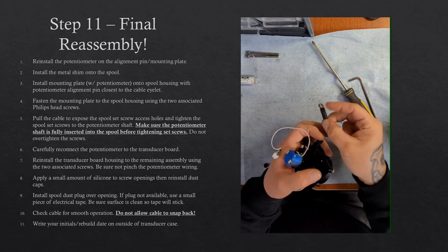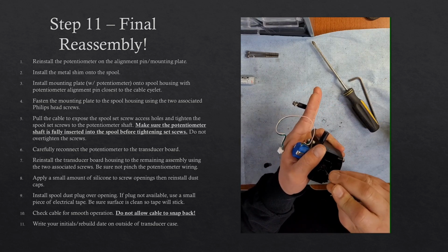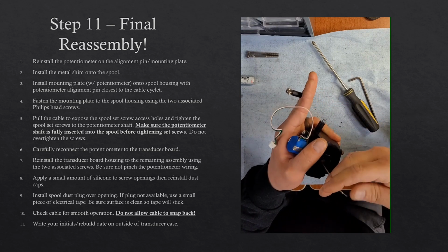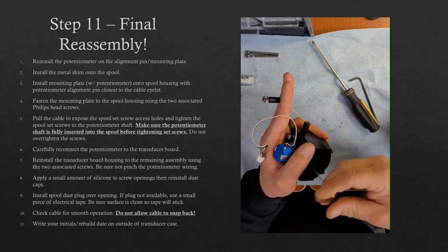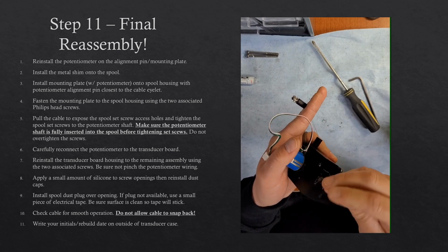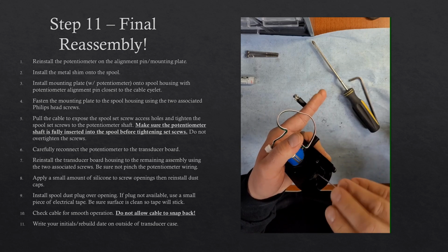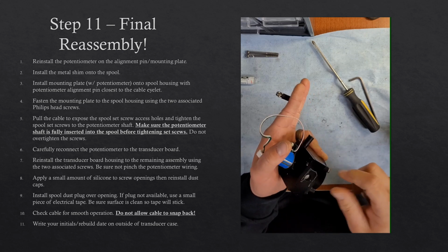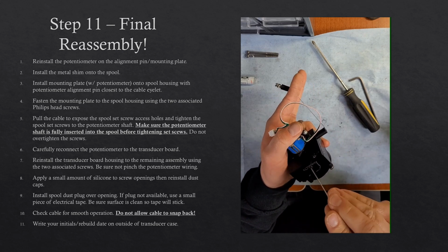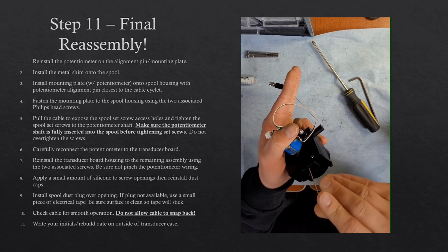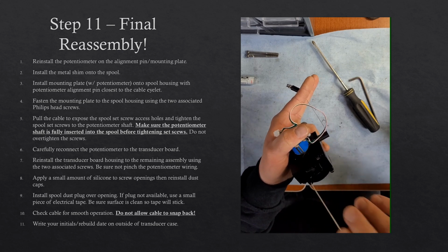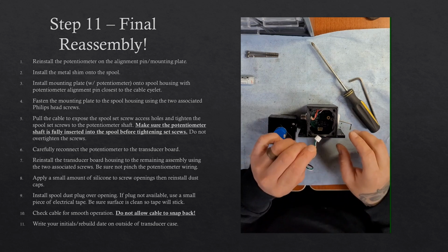we're going to move over to the set screws on the spool. So again, pull that cable out until you can get access to those set screws. We're just snugging those up. They don't need to be super tight. And again, don't use a ball end, because you could potentially snap the ball end off inside of the set screw. Remember, there are 2 set screws. You got to get both of those snugged up.